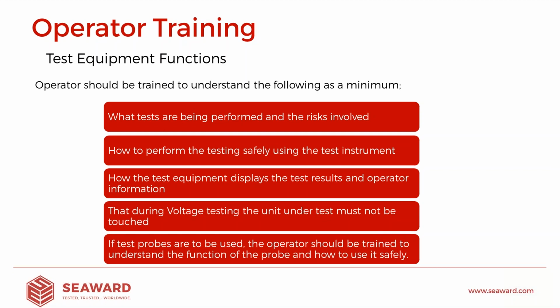They should obviously understand that during the testing, in no way, shape or form should they be in contact with the product, unless of course we're using probes. And therefore, if they are using probes and having to make physical contacts manually, they should fully understand exactly how those probes are used. So if the probe has retractable tips, for example, they need to be trained to understand that when they make contact with the product, the tip shouldn't be exposed, the product contact should be made, and then the tip placed into position until the contact is met. But there's no exposed metalwork. So if you are using probes, again, make sure the operators fully understand exactly the functions of the probe, exactly where it needs to be to make a good measurement, but ultimately how to use it to perform a safe measurement.